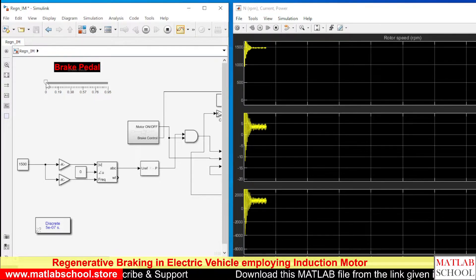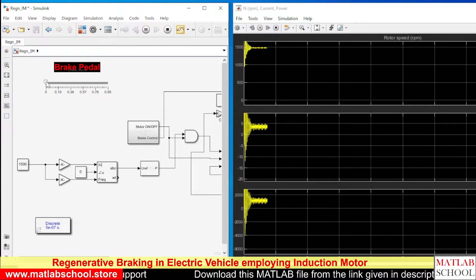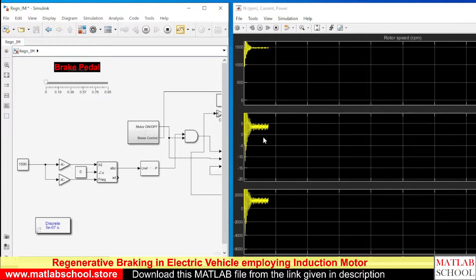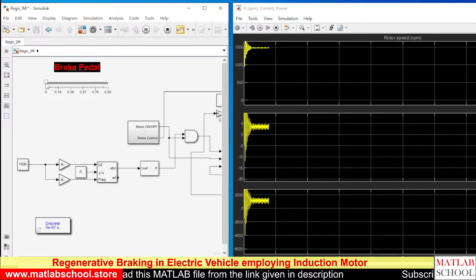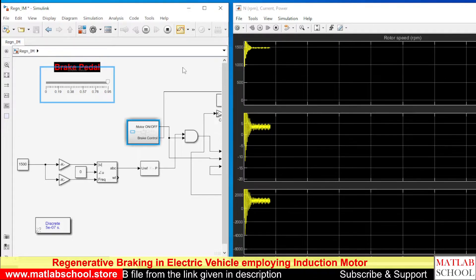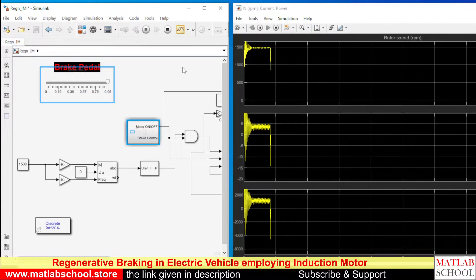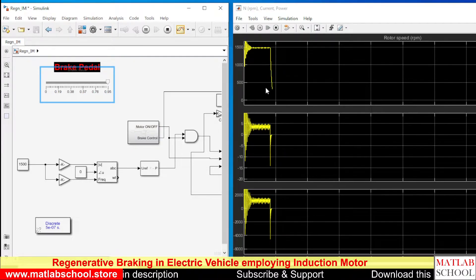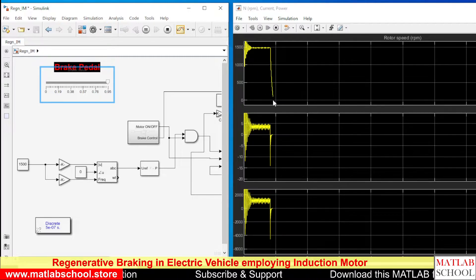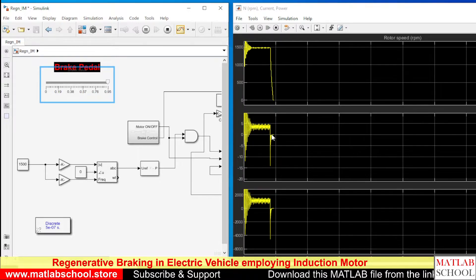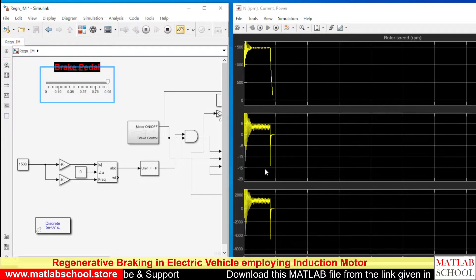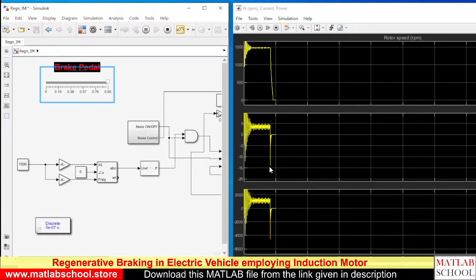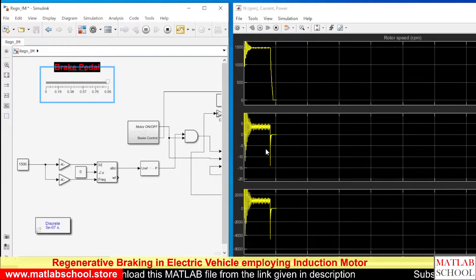You can see the change in speed as well as the change in current and power. I am going to apply extreme braking now. You can see the speed going to zero and whenever we apply the brake, you can see the current going in the negative direction. See the spike in current.